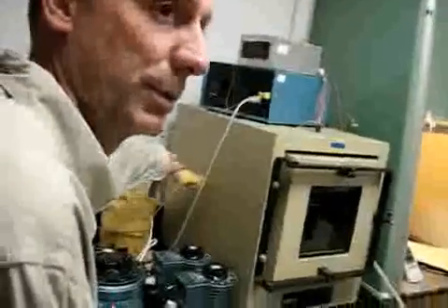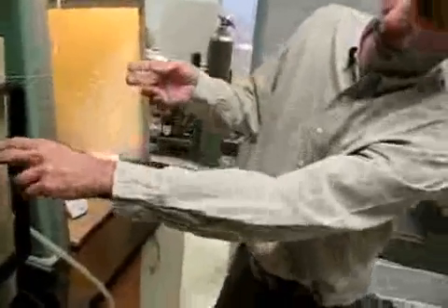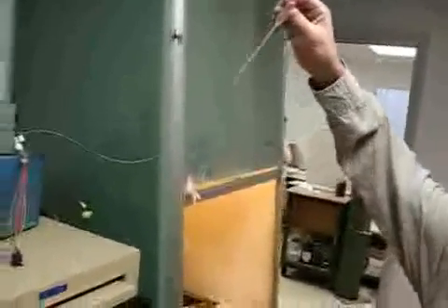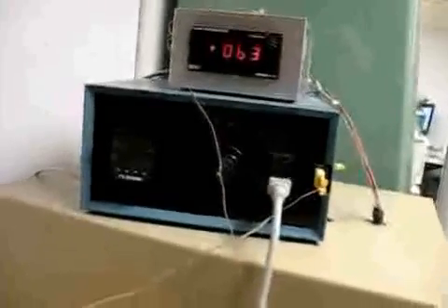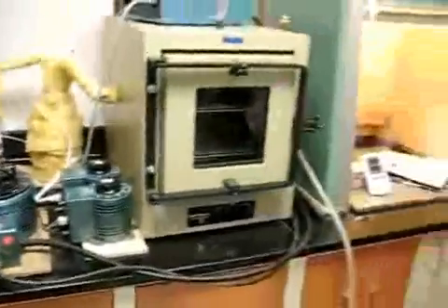That's not perfect for various reasons, whether it may be a little sub or super saturated from that value. We can monitor in here in 2 different ways. We have a relative humidity sensor, and we have what I believe is the more reliable wet bulb, dry bulb technique, whereas right in the wind field of this fan, we have a wet bulb and a dry bulb. The wet bulb, we have the ability to add water, and we can see the bulb and when it is wet, and take a wet bulb and dry bulb measurement and calculate the dew point from that. And see that we're getting reasonable agreement with the desired dew point and our other measurement of relative humidity.